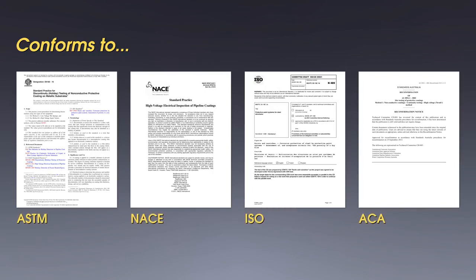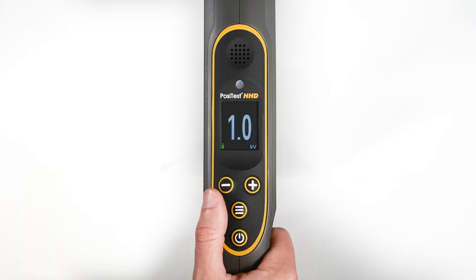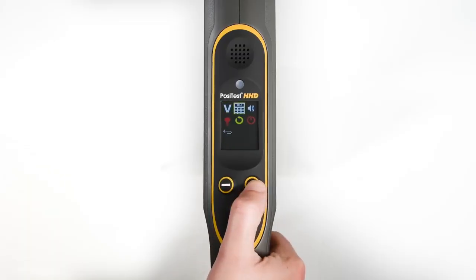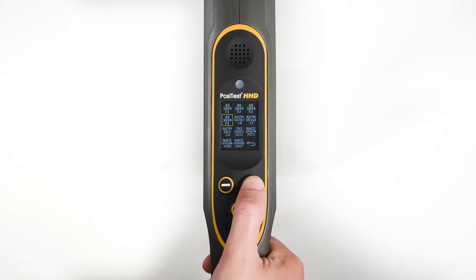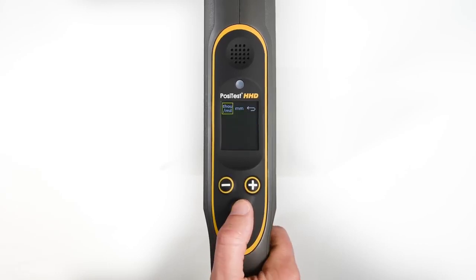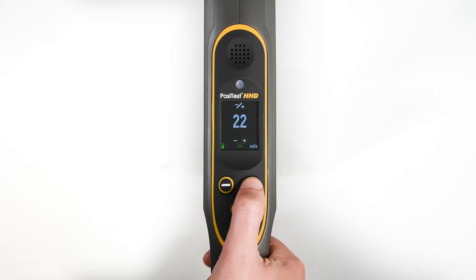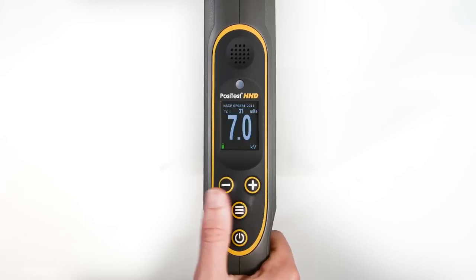The convenient voltage calculator feature makes following them easy by automatically calculating a test voltage without the need for lookup tables or complex math. Select the voltage calculator option from the menu and choose the desired test method. As the dry film thickness of the coating is adjusted, the proper test voltage is automatically calculated.